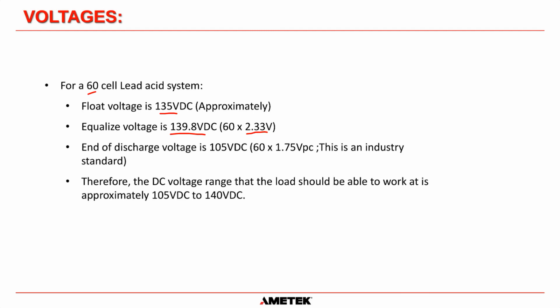And then the end of discharge voltage is usually stipulated as 105 volts DC in the industrial world. And that is 1.75 volts per cell times 60. Because in a lead acid battery, you don't want to let the voltage get below 1.6 volts per cell. Once you go below that level, you can start to do irreversible damage to the plates by over discharging, and the sulfation takes hold much more below that voltage. So all the manufacturers say do not discharge your lead acid battery below 1.6 volts per cell. Therefore, the DC voltage range that the load should be able to work at is approximately 105 to 140 volts DC. And that's what we're concerned about.